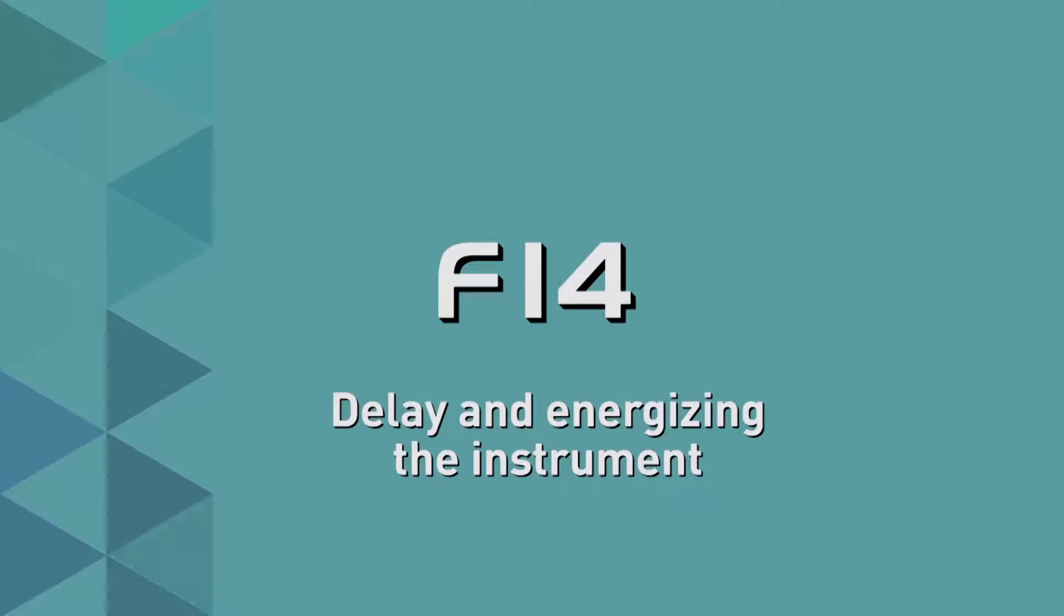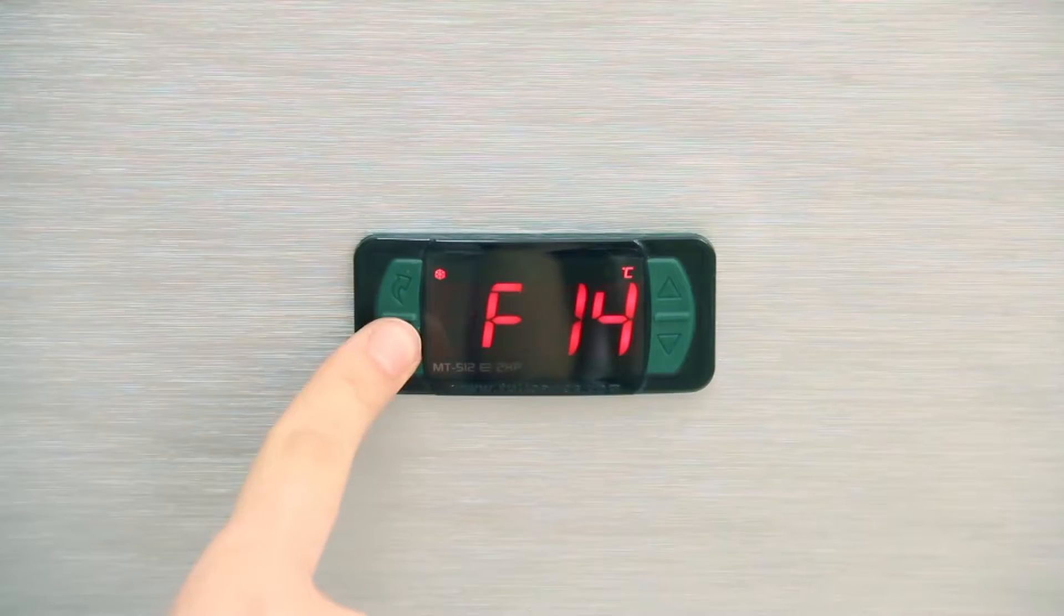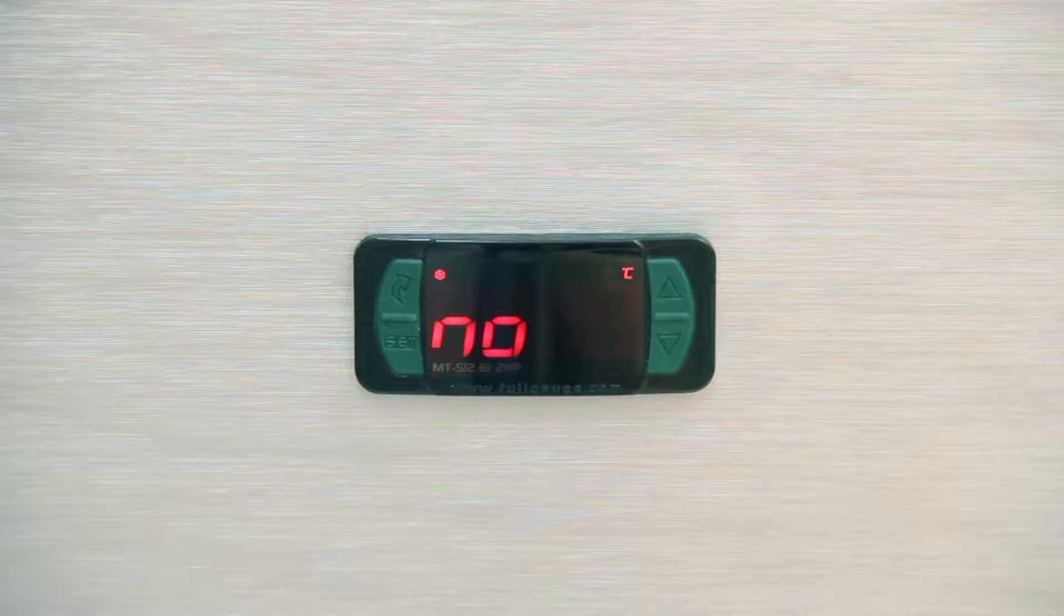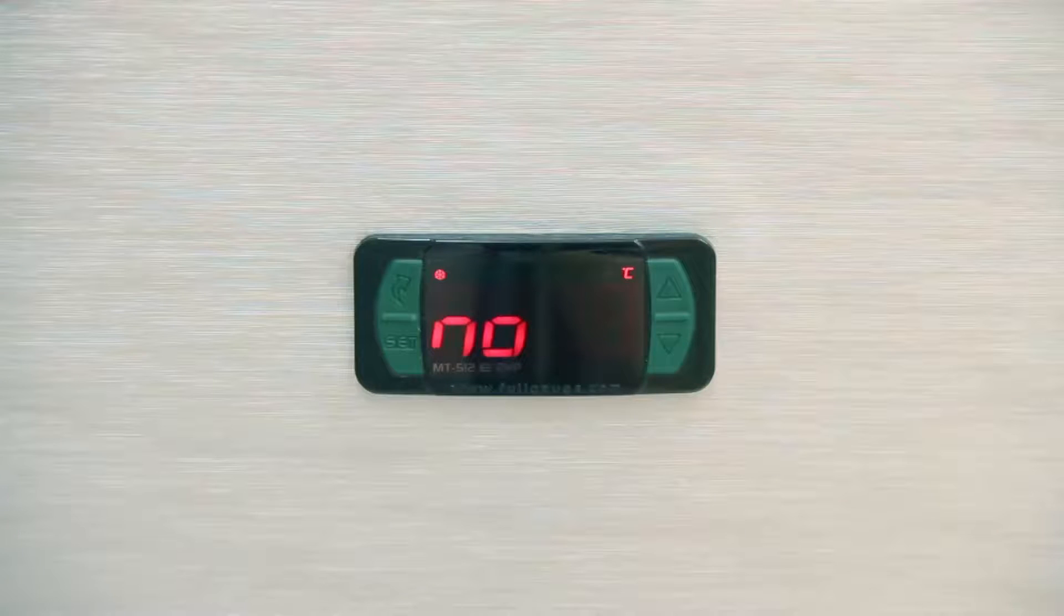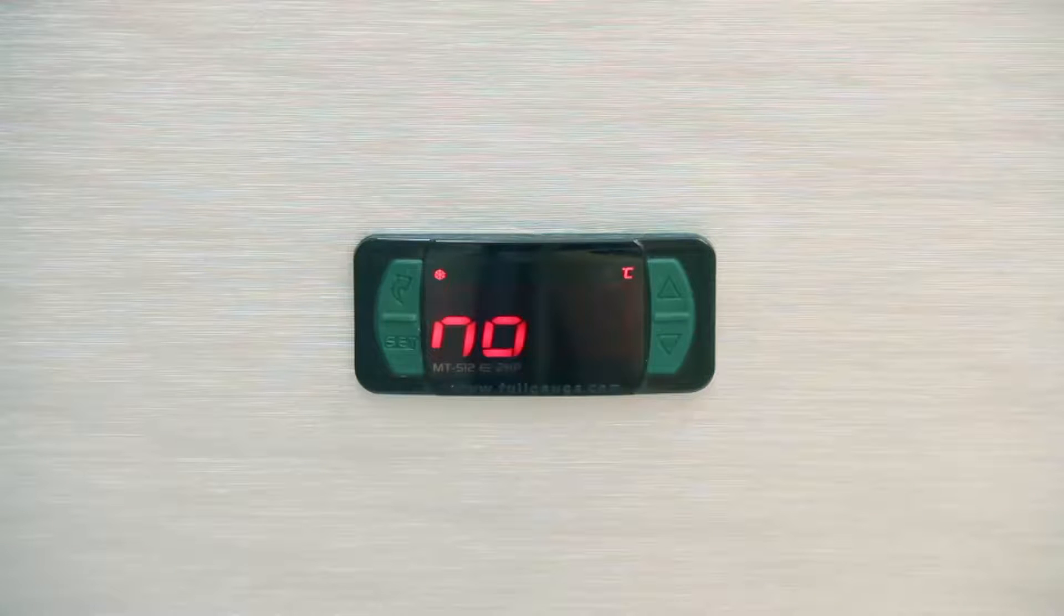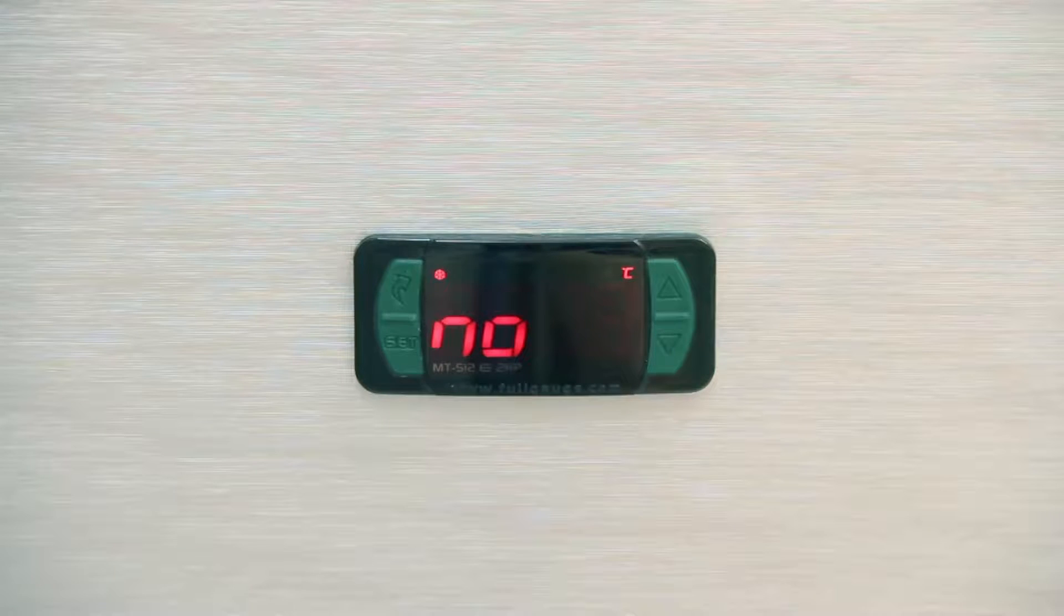F14, Delay in Energizing the Instrument. This setting prevents the generation of electricity demand peaks in the event of failure and return, when there are multiple devices. Select No, so as not to delay the energizing. If you choose a delay, provide a time of 1 to 240 minutes. In the examples, we chose not to adopt the delay.